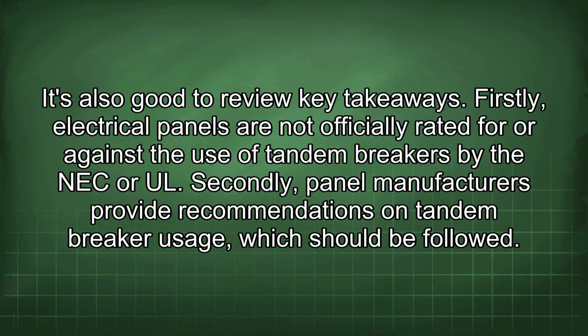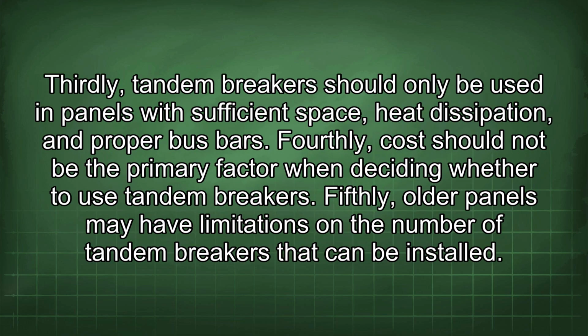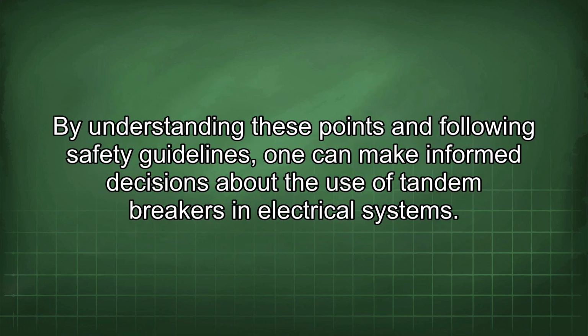It's also good to review key takeaways. Firstly, electrical panels are not officially rated for or against the use of tandem breakers by the NEC or UL. Secondly, panel manufacturers provide recommendations on tandem breaker usage, which should be followed. Thirdly, tandem breakers should only be used in panels with sufficient space, heat dissipation, and proper bus bars. Fourthly, cost should not be the primary factor when deciding whether to use tandem breakers. Fifthly, older panels may have limitations on the number of tandem breakers that can be installed. By understanding these points and following safety guidelines, one can make informed decisions about the use of tandem breakers in electrical systems.